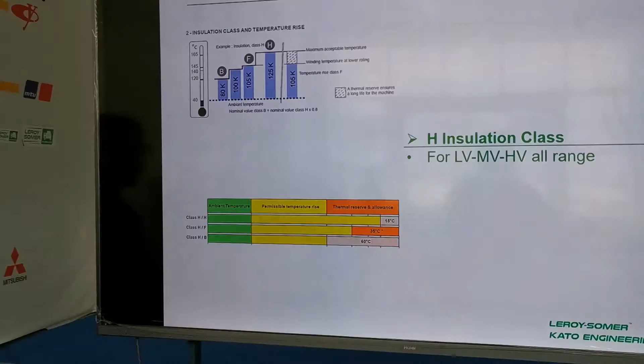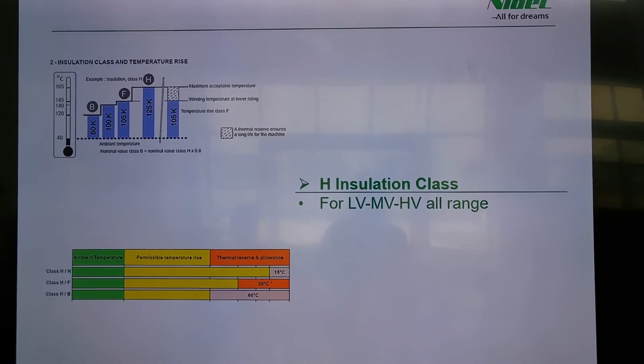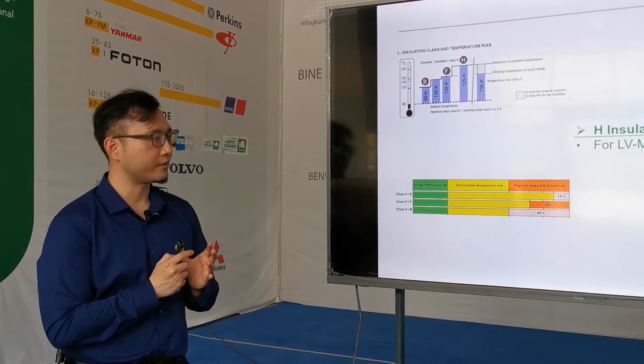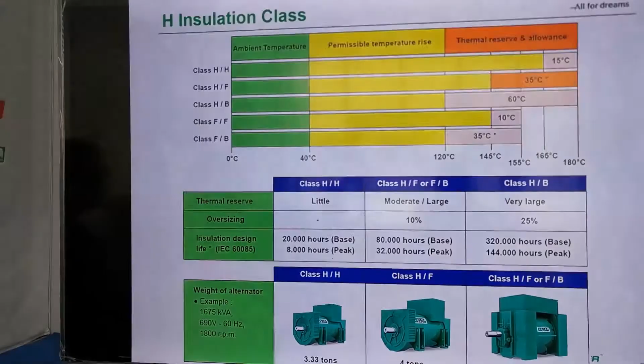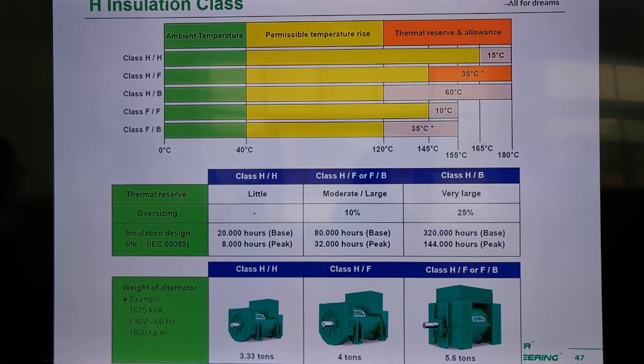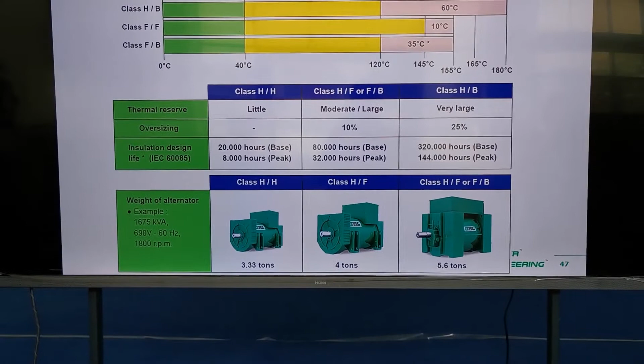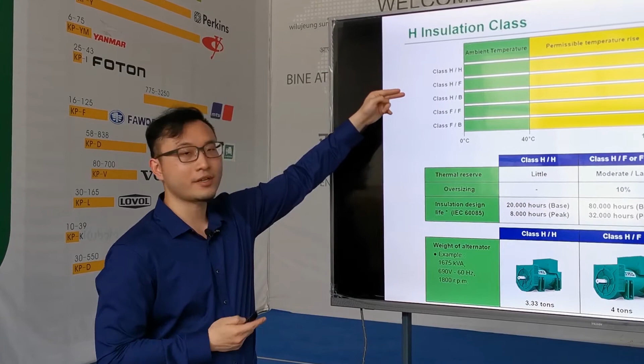And the last one is the H insulation class. For Leroy Somer products, no matter low voltage, medium voltage or high voltage, the whole product range uses H insulation class for the insulation system. Here is just some introduction about the H insulation class system. Normally, if we see the product catalog, you will see something like class H/H, or H/F or H/B.